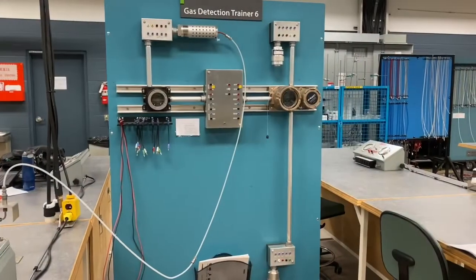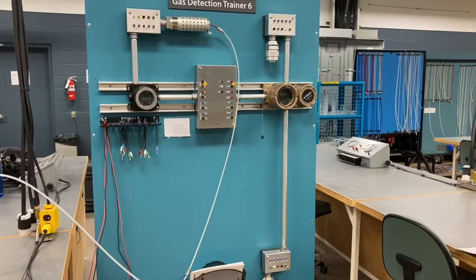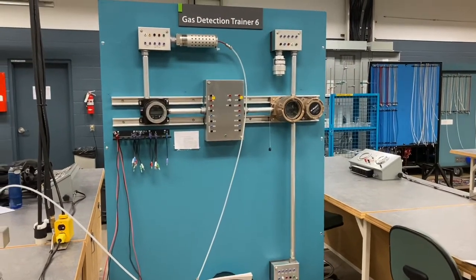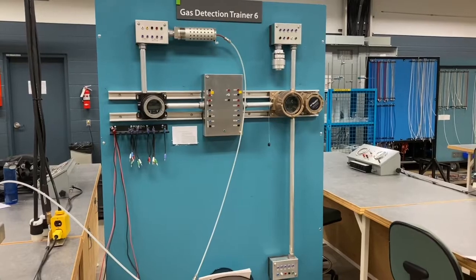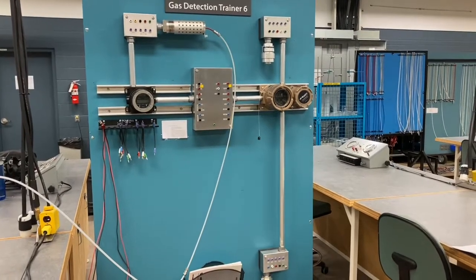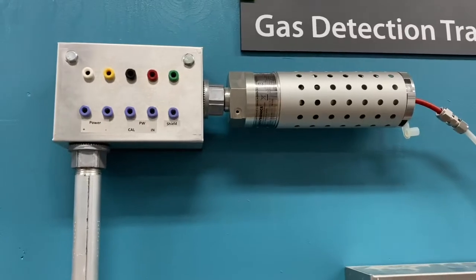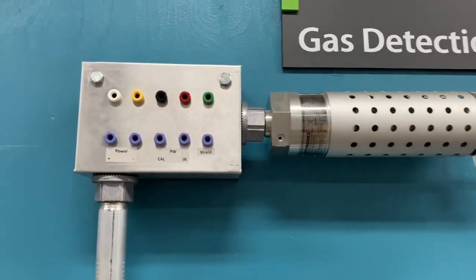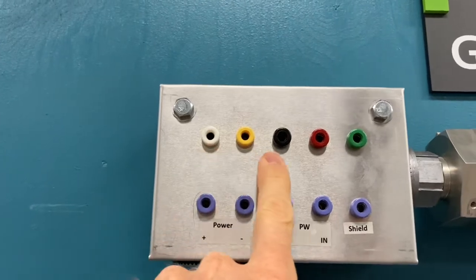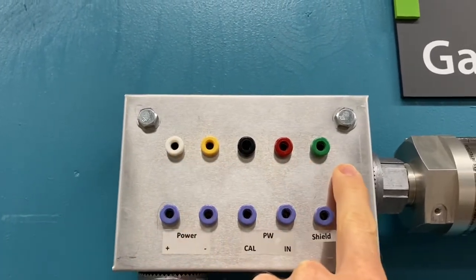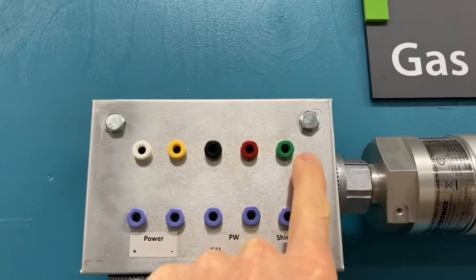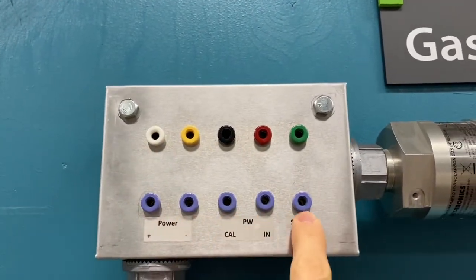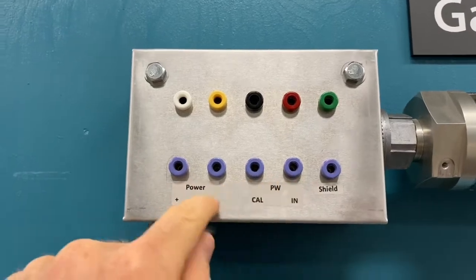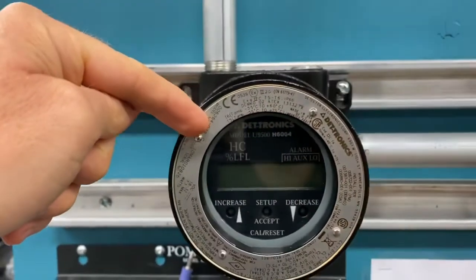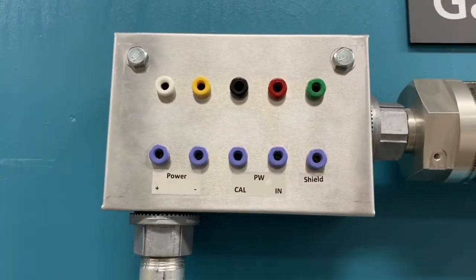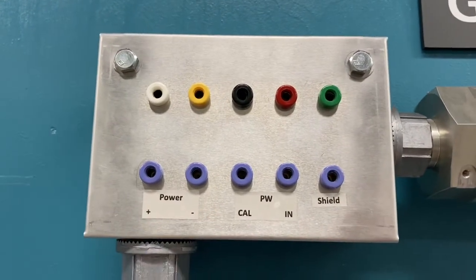Right, so I'm going to go ahead and wire up both the systems here for using the LEL sensor. There will likely be some questions on the wiring. You have to refer to the manual for that to answer those questions. Before I wire up the PointWatch Det-Tronics sensor up here, the infrared sensor, I just wanted to point out that it has the color-coded wires, just like the net safety system, the way that we've set it up. So the wires come out of here and they're color-coded just like this, and then these purple banana connectors run down to the conduit into the Det-Tronics housing here as well. So when you're looking up the wiring in the manual, if you need to refer to that, this is where it is on the trainer.